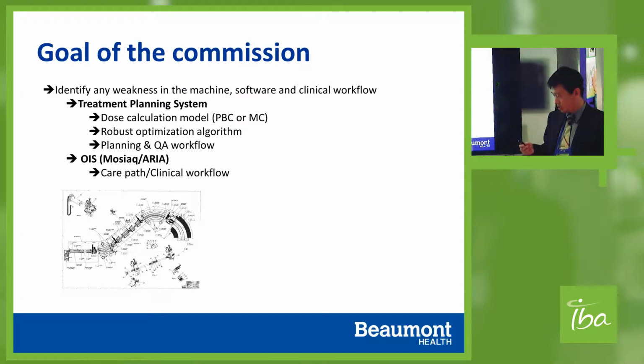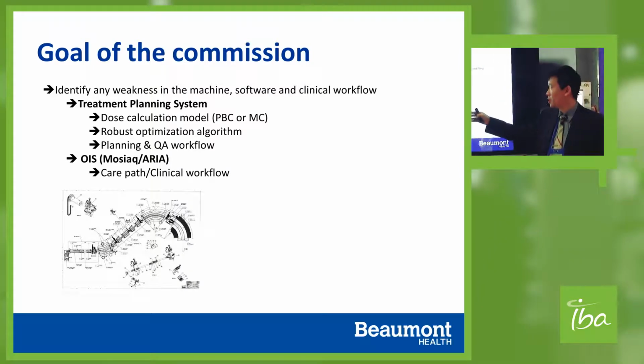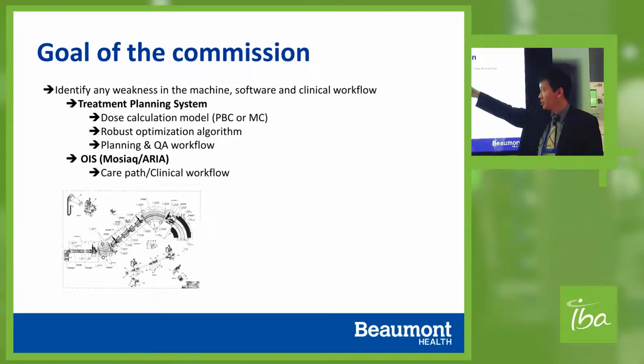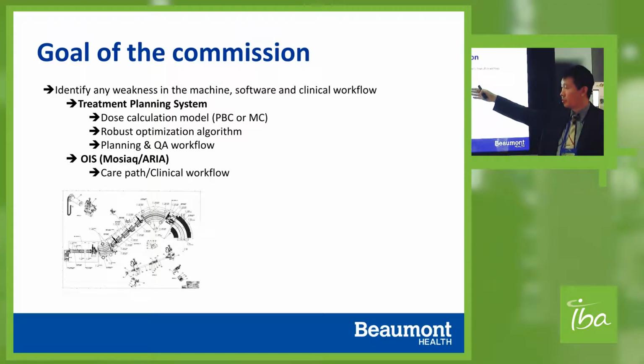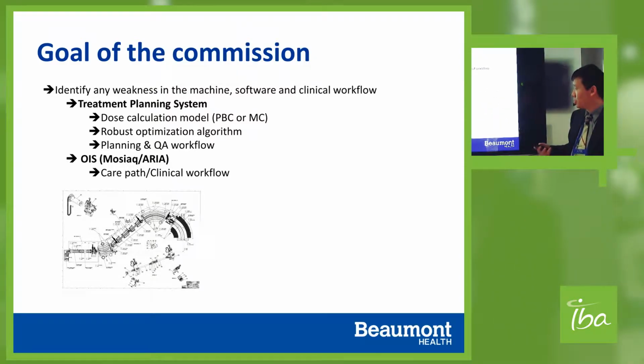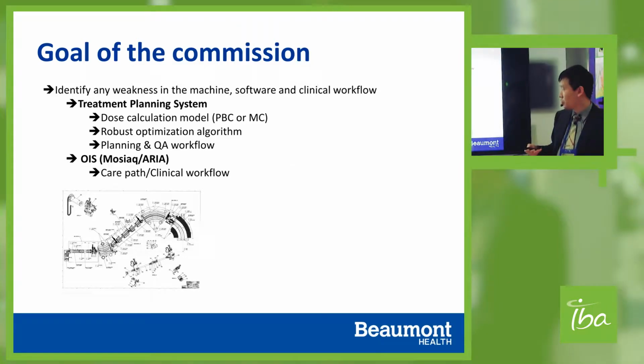So in terms of the goal of the commissioning, we're not just working on the beam data, collecting the beam data. We're also working on all the workflow from the treatment planning system, your OIS, depending on if you're using the Mosaiq and ARIA, to find out what's your limitation, why you need to do that.